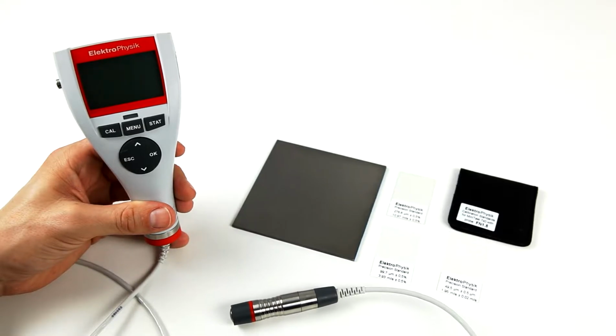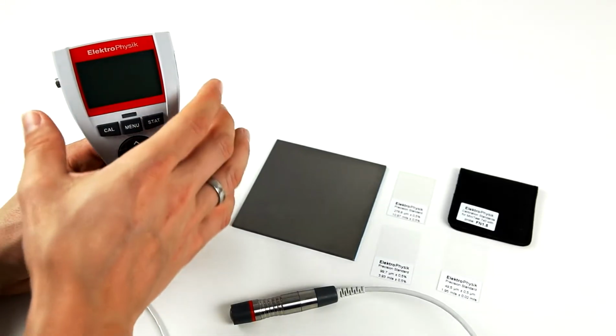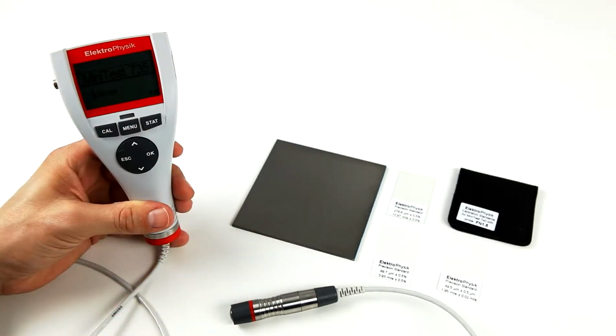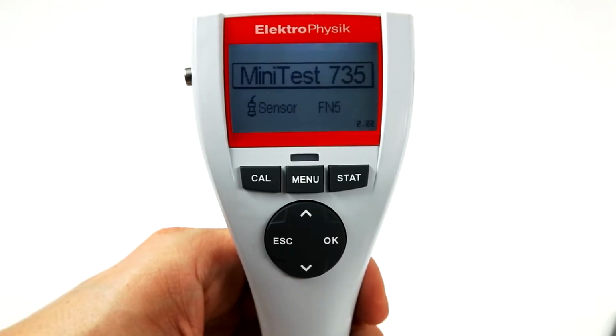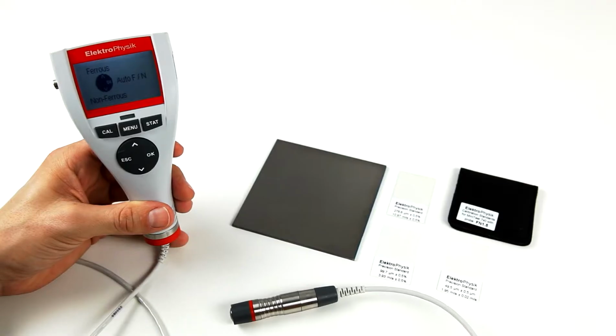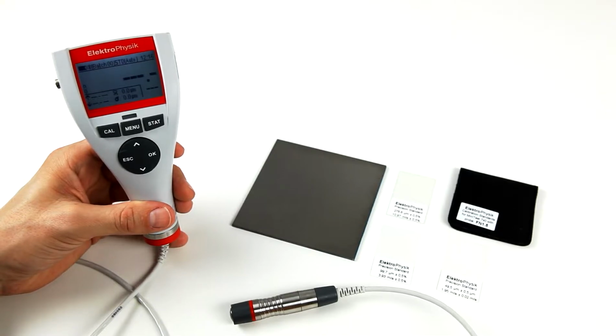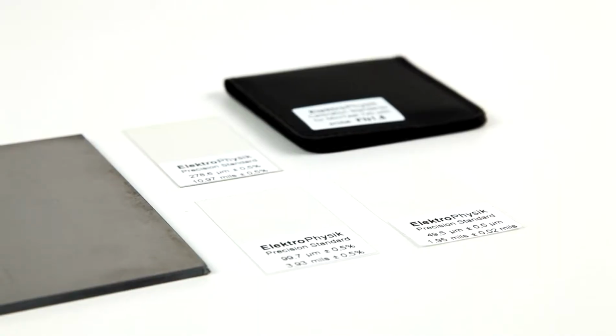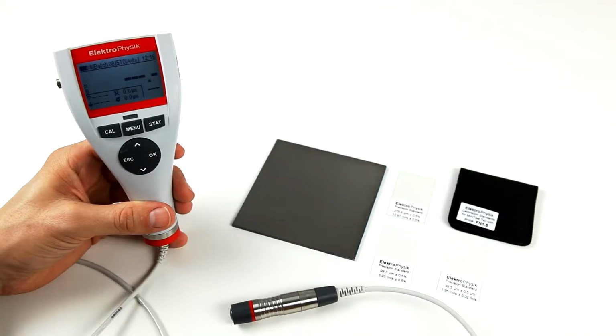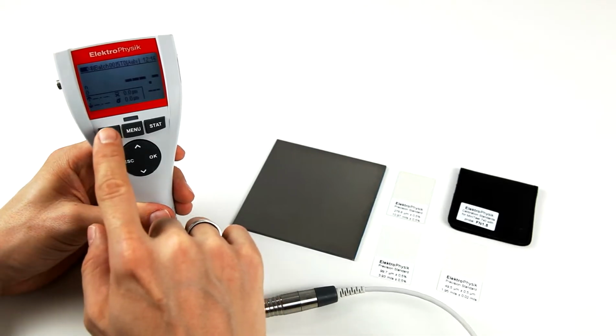The MiniTest 725, 735 and 745 family offers gauges of various models to measure the thickness of non-magnetic coatings on magnetic substrates and non-conductive coatings applied on non-magnetic metal substrates. Ideally, the MiniTest gauge should be adjusted to suit each specific measuring task. It is recommended you calibrate the gauge using the calibration foils, which are placed on an uncoated sample. This calibration will be illustrated with a MiniTest 735 equipped with an FN sensor.